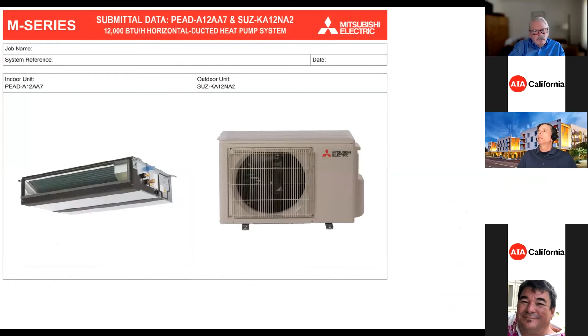We really love what manufacturers, especially Mitsubishi and Fujitsu, are doing with minisplits, especially the ducted version. They're small, compact, come in a variety of sizes, and have SEER ratings of 20 compared to 14. The variation in sizing is great because I can precisely match the load. Again, the higher the SEER rating, the better; 14 is our minimum, and I'm looking at 20.